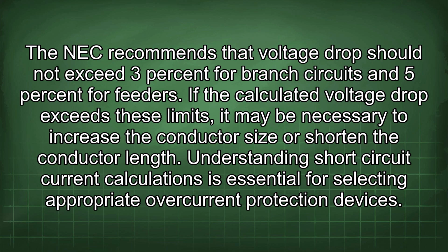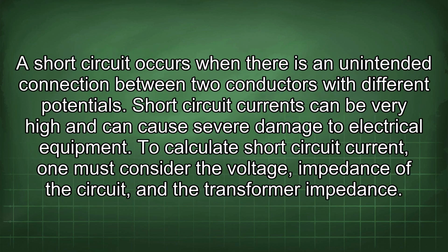If the calculated voltage drop exceeds these limits, it may be necessary to increase the conductor size or shorten the conductor length. Understanding short-circuit current calculations is essential for selecting appropriate overcurrent protection devices. A short circuit occurs when there is an unintended connection between two conductors with different potentials. Short circuit currents can be very high and can cause severe damage to electrical equipment. To calculate short circuit current, one must consider the voltage, impedance of the circuit, and the transformer impedance.